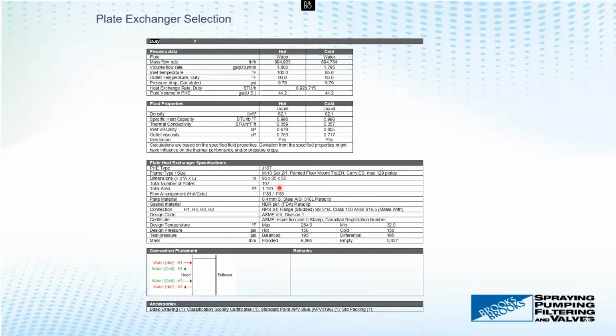This heat exchange area is going to be just over 1,100 square feet. It's going to be ASME Section 8, it's going to have a U stamp, it's going to be CRN registered, and then some shipping dimensions and weights down here. So when it's full of fluids it's going to be essentially 6,000 pounds, and empty it's going to be 5,300 pounds. Pretty big machine, but it does a tremendous amount of heat exchange, 9 million BTUs.